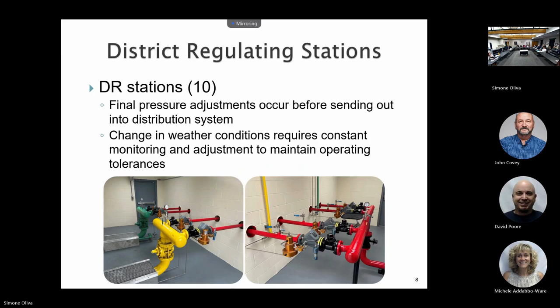These guys do a great job, as you can tell by this station - this wasn't cleaned up just to take the picture, this is how they operate and maintain these systems. Sometimes they're in there at 3 o'clock in the morning dealing with a low pressure or temperature situation, so it helps to have a clean, comfortable environment to work in. These are open to the atmosphere, not climate controlled - they have open vented doors, so whatever the temperature is outside, they're working in it too. Sometimes we require heaters inside these spaces to keep them to temperature.